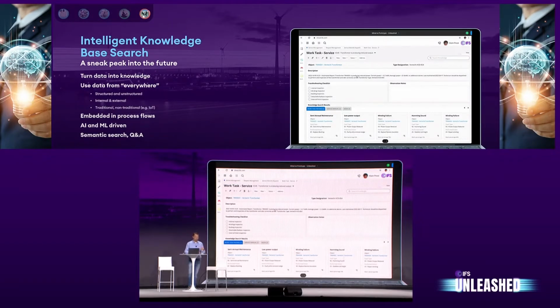And the system, based on the templates it has, says that to handle such an issue, there's a number of things I need to inspect. I need to do an internal inspection, a winding inspection, a bushing inspection, all kinds of inspection. But what's more interesting is we see at the bottom the knowledge search results. Based on all the data in this work task, the asset type, the IoT readings, it has looked in its historical data sets and starts bringing together tasks that have similar data patterns, that could be similar to the problem that we look at now.